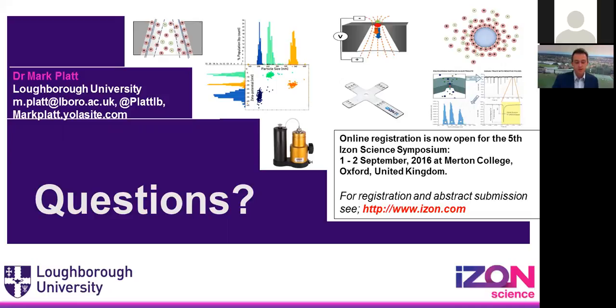If you can see a nice pulse and you've got a nice calibration, then the pore size in a calibrated system should be okay, within a stretch. If I have a small NP100 or a 200 and I change the stretch, as long as I can see a nice pulse, that won't really impact your measurement too much. If you change the pore size by going to an NP4000 and try to measure a Zeta potential value there, it becomes more complex, because as I showed you in one of the earlier examples of Zeta potential measurements, if you increase the fluid flow through the pore, the flow of the liquid can completely dominate the speed of the particle.